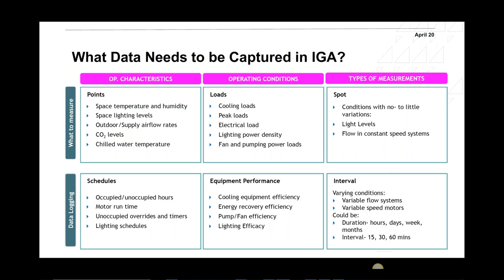There are some spot measurements that need to be taken. Let's say I see a pump that is constant speed, or a fan that is constant speed, say an outdoor air handling unit sitting on the roof, working 24/7. I really don't need to put a meter on for more than a short amount of time, just to see what the power consumption is. Then I can multiply by the assumed hours that I know from the facility management or from the BMS trends, that this equipment is running 24/7, 8,760 hours a year, basically. Light levels, that's spot as well. Flow in a constant speed system, that's a spot measurement.